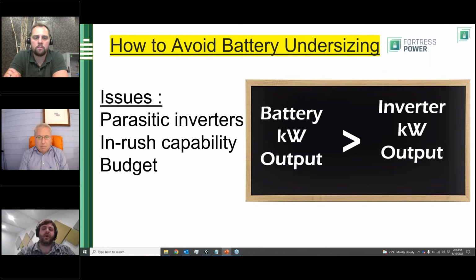In our Battery 101 class, we get into looking at the data sheet on the battery. The data sheet has a kilowatt output rating, and the inverter has a kilowatt output rating - make sure the battery kilowatt output rating is greater than or equal to the inverter kilowatt output rating. If not, not only are you buying inverter capacity you won't use, but you could run into lesser-known design issues involving the inrush capability of the inverter compared to the battery.